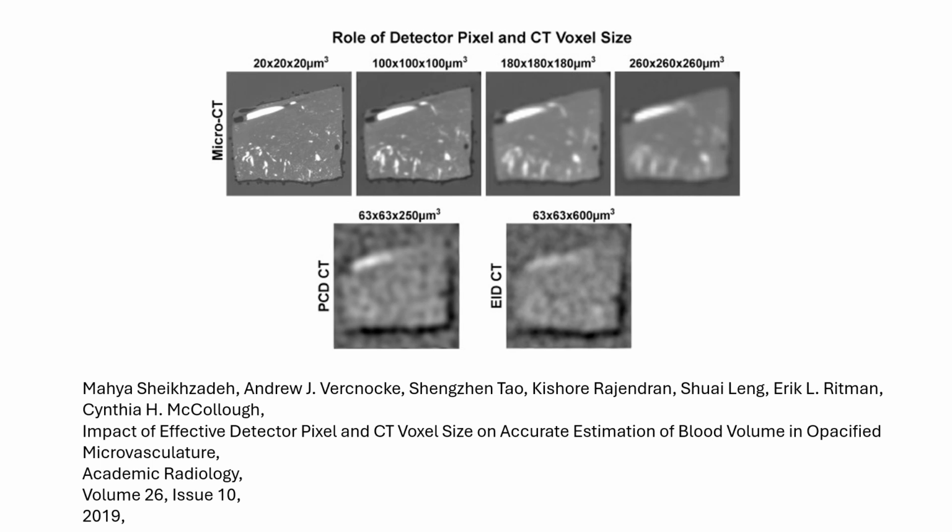The lower images are for whole body CT systems, where the resolution is more on the hundreds of microns or even a millimeter scale. This is comparing a photon counting detector with an energy integrating detector on these scales. So for an X-ray system, resolution is not determined by wave diffraction. It's going to be determined by how much material you need to go through to see some modulation. And then once you know that material size, then you can design a code and a detector to match that.